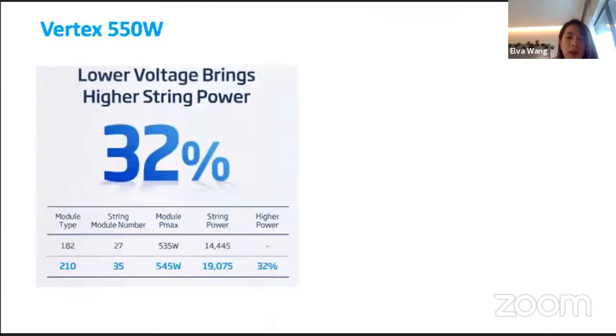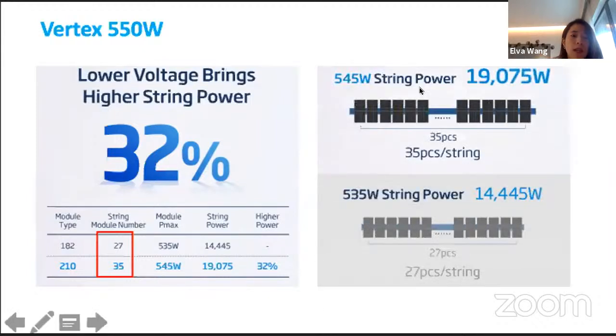So why do we need to refresh the VOC parameter? Let's say currently all solar farms are around 1,500 voltage. If you're using the 210, 545 watt module, one string you can connect 35 pieces, so one string power is around 19 kilowatt.